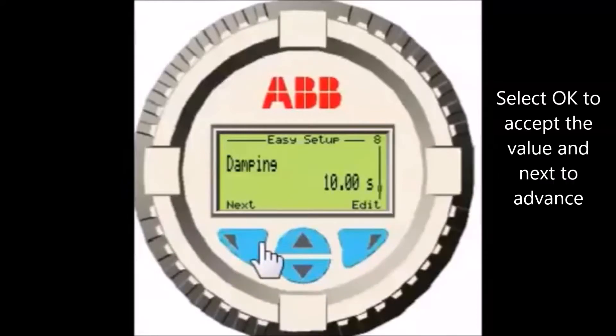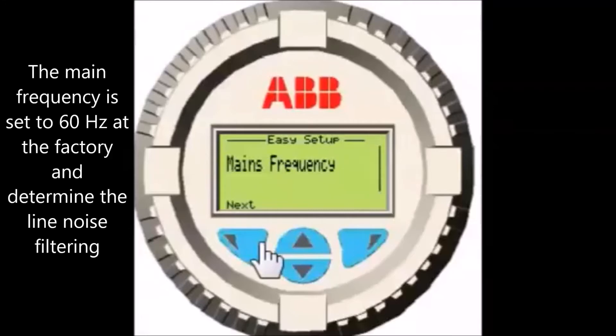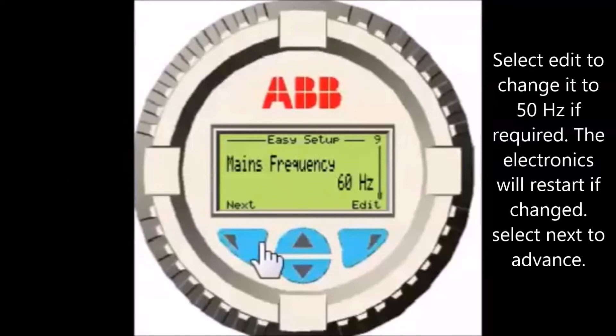Mains frequency is defaulted at the factory for 60 Hz, the US standard. If required, select Edit and select 50 Hz. If your power source is 50 Hz, then select it. This setting determines the line noise filtering. Select OK to accept the value and then select Next to advance.